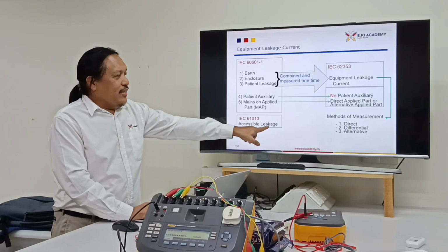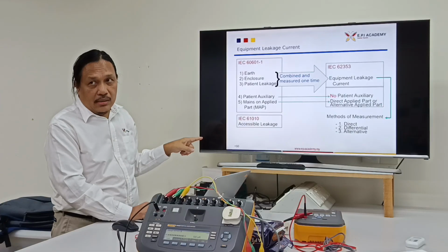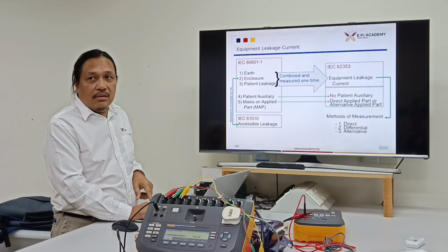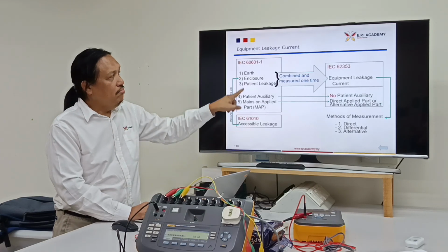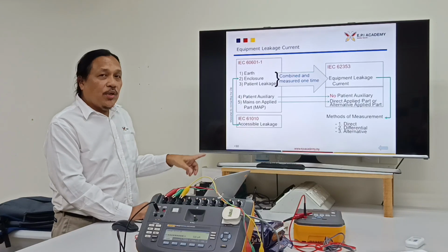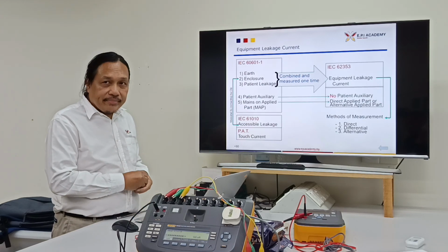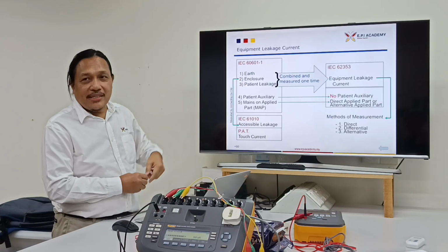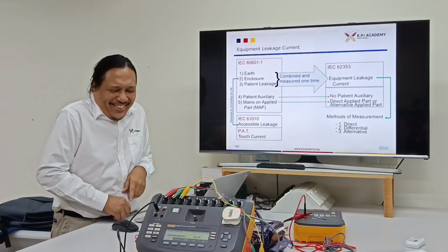How about 610? What is accessible leakage compared to 60601? Is it the same as enclosure leakage? Different standard, different name. Same. How about PAT, portable appliance test, for non-medical equipment? It's called touch current. What is this? Patient leakage. It's the same as enclosure leakage also.